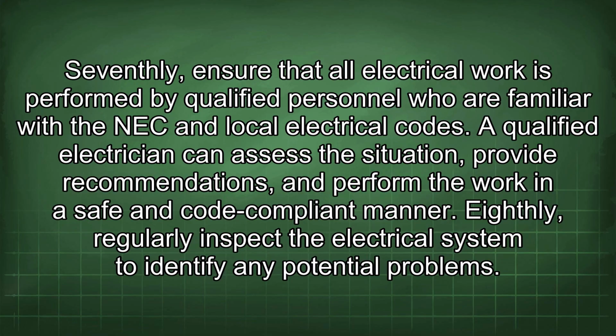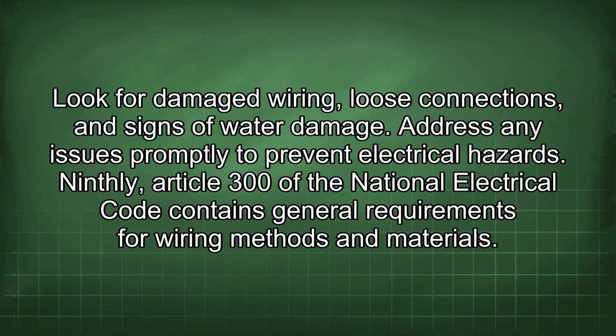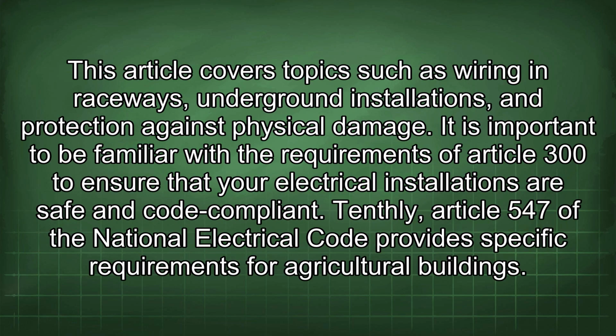Eighthly, regularly inspect the electrical system to identify any potential problems. Look for damaged wiring, loose connections, and signs of water damage. Address any issues promptly to prevent electrical hazards. Ninthly, Article 300 of the National Electrical Code contains general requirements for wiring methods and materials. This article covers topics such as wiring in raceways, underground installations, and protection against physical damage. It is important to be familiar with the requirements of Article 300 to ensure that your electrical installations are safe and code compliant.